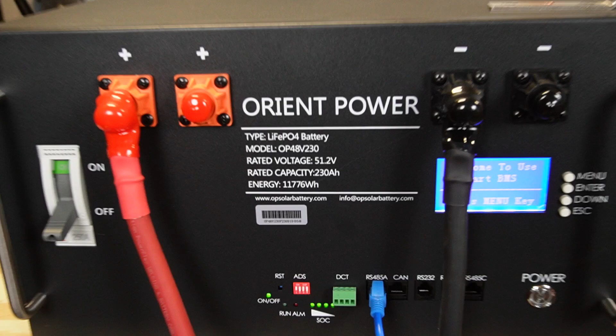Over here on the left side is a 250 amp breaker. If you turn it on and it trips, here's actually a trip test button, it puts it in the middle so you know it wasn't turned off, it actually tripped. This breaker physically disconnects the positive terminals to the battery inside.